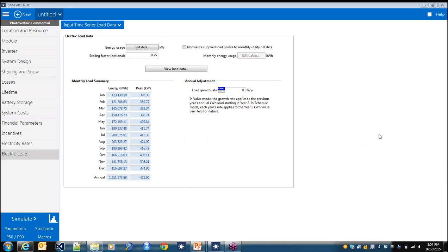So, a comment from David: I assume you mean peaks are equally valued per kilowatt shaved. Yes, that's correct. It's a fairly naive automatic dispatch controller that will initially be released, and as David says, it doesn't assume anything about the peaks. It just assumes that you want them as low as possible over each 24-hour period. The time of use rate, it doesn't care about that.